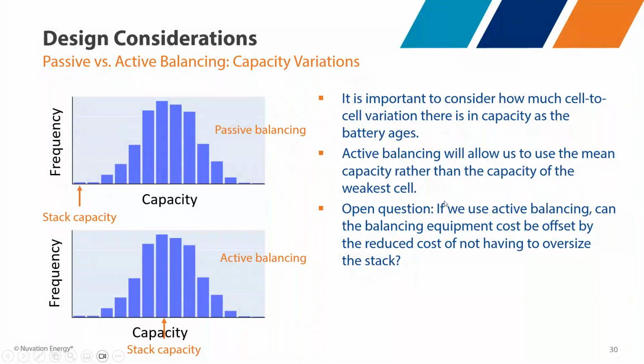An open question to consider: if we use active balancing, can the balancing equipment cost be offset by the reduced cost of not having to oversize the stack? This really depends on the application. What we've seen in the industry is that as node sizes continue to increase, the economic argument for active balancing is becoming more compelling. We're seeing more situations where active balancing does pencil out in the total cost of ownership of an energy storage system.